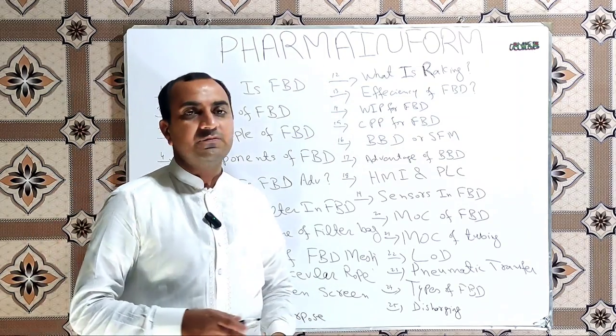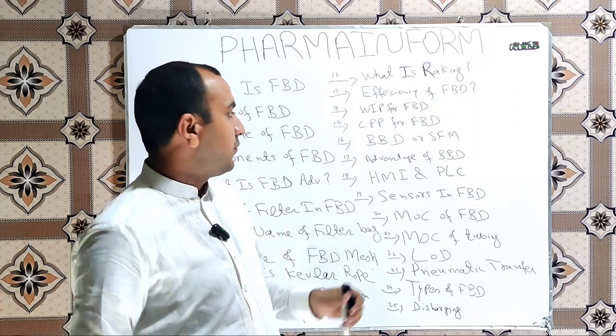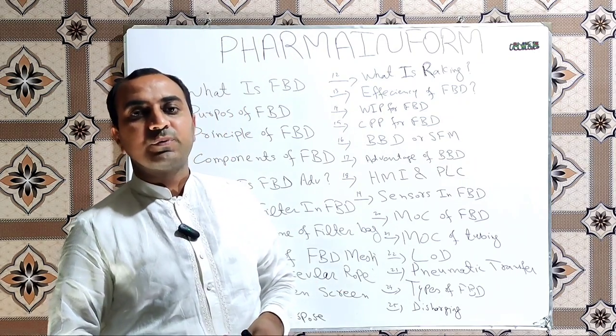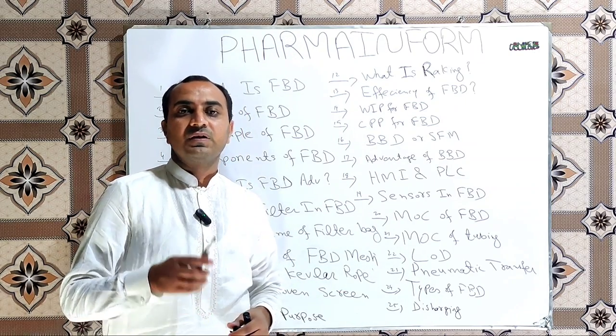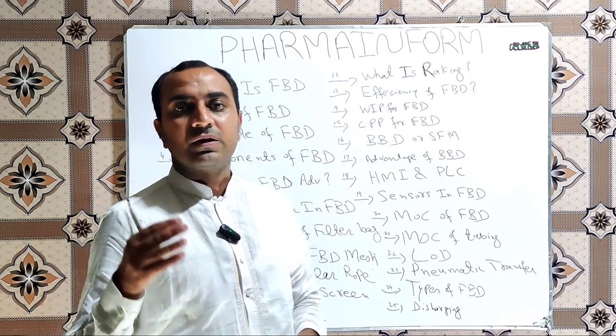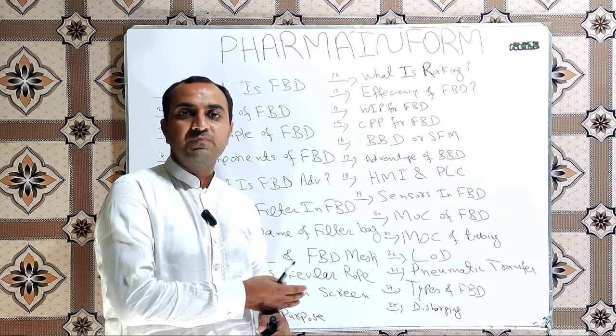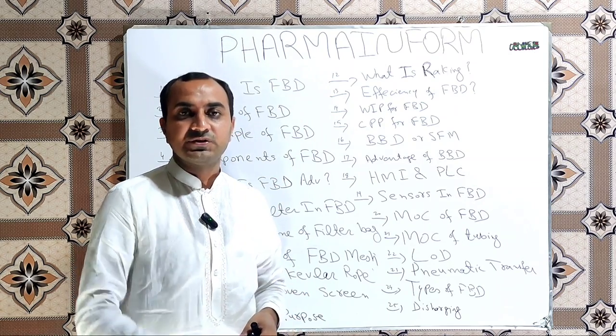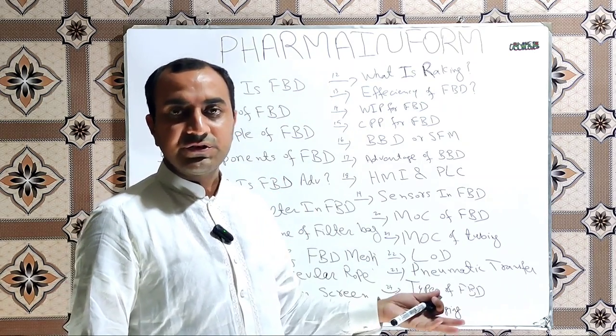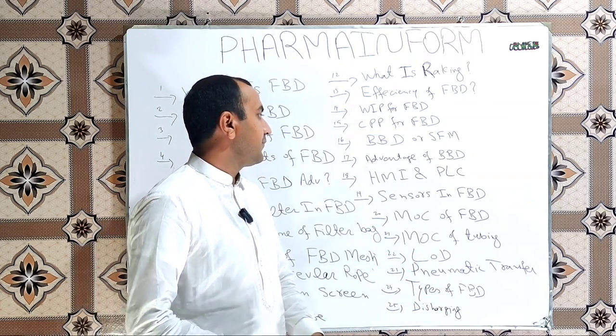What is the CPP for FBD? What are the critical process parameters for FBD? Usually critical process parameters for FBD are temperature of inlet air, temperature of outlet air, temperature of our product, and airflow volume meaning fluidization pressure. These are the critical parameters of FBD.